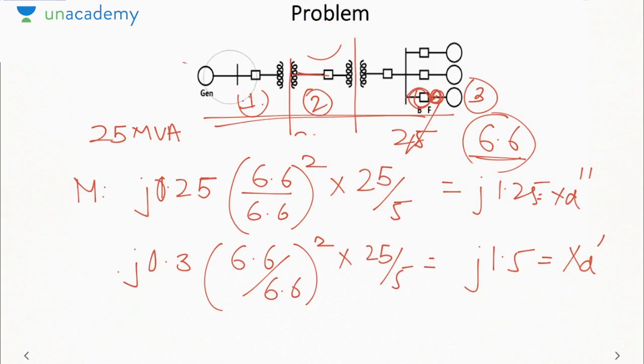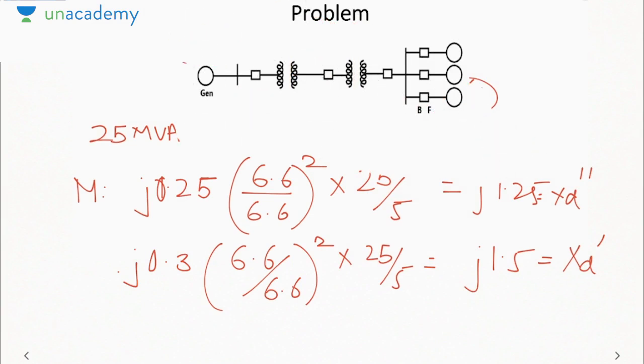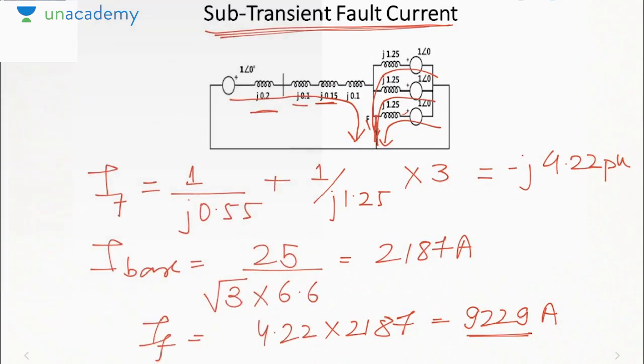See, if the current from the generator goes into the fault, it has to go through the breaker. It will go like this. For this machine, if it goes into the fault, it has to go like this through the breaker. For this machine, if it goes, it has to go like this through the breaker. But for this machine, it can directly go into the fault without going through the breaker. So only three currents will pass through the circuit breaker. One will go directly into the fault.